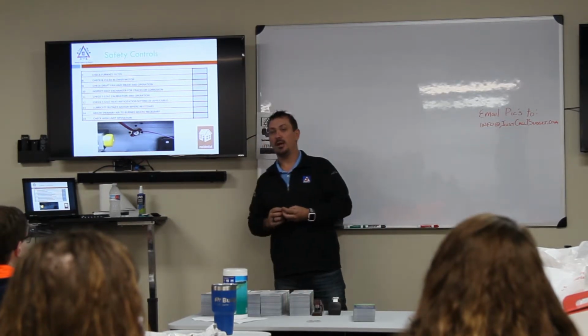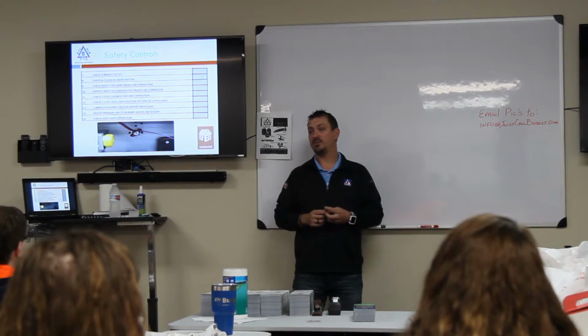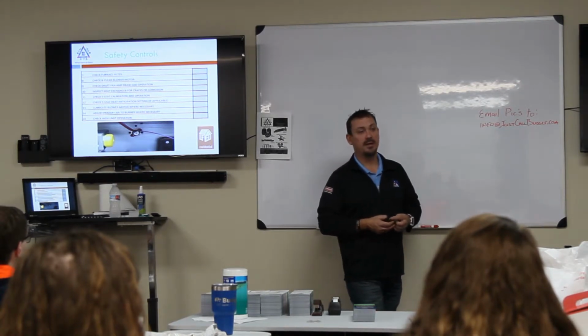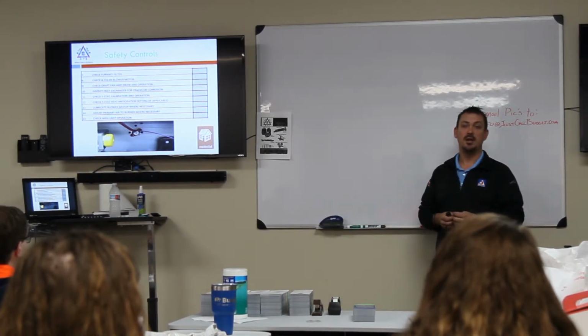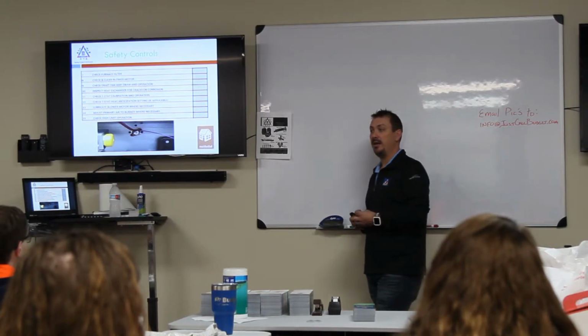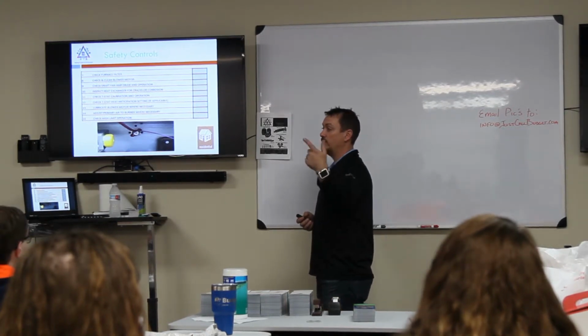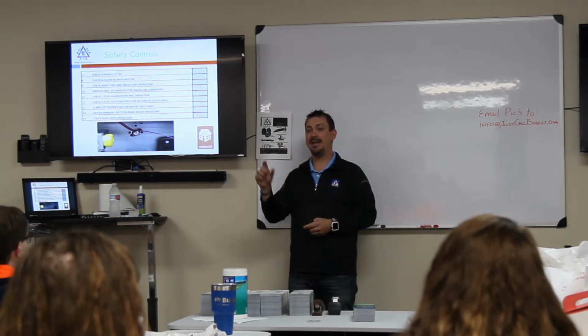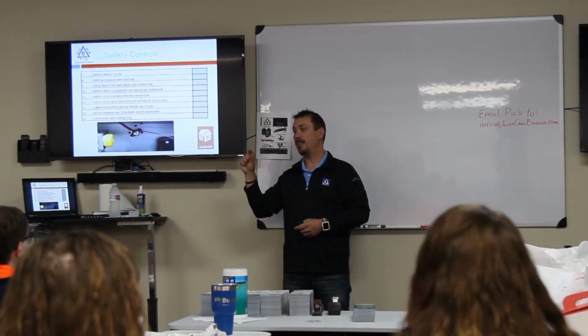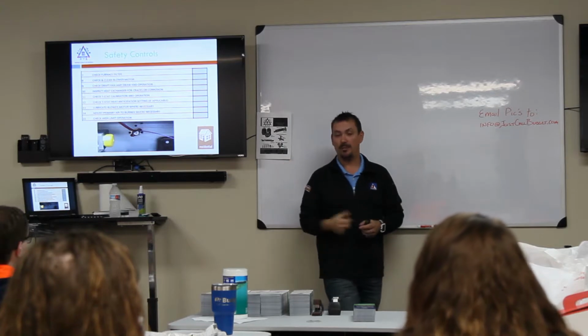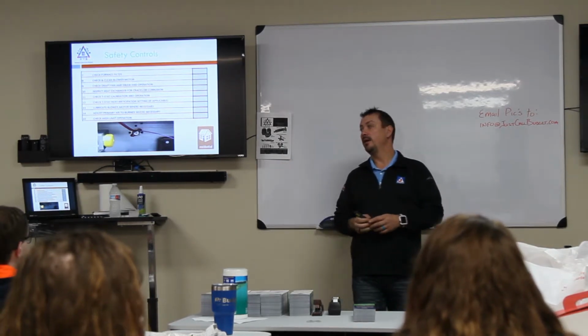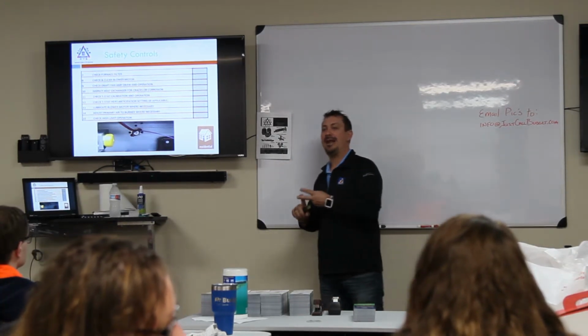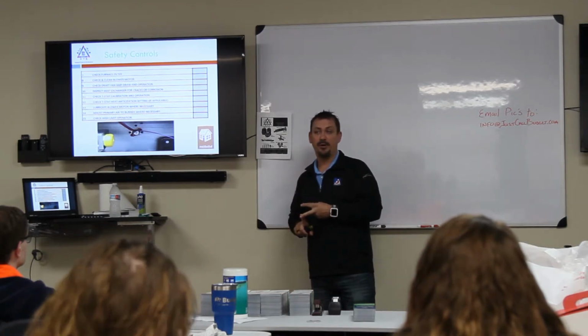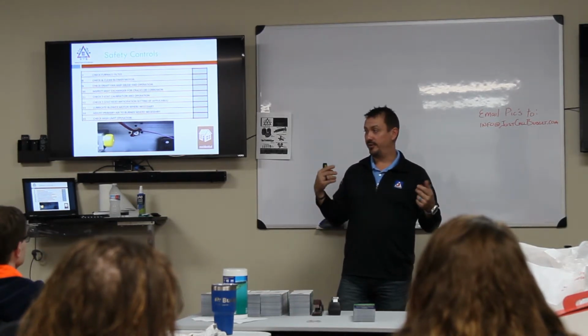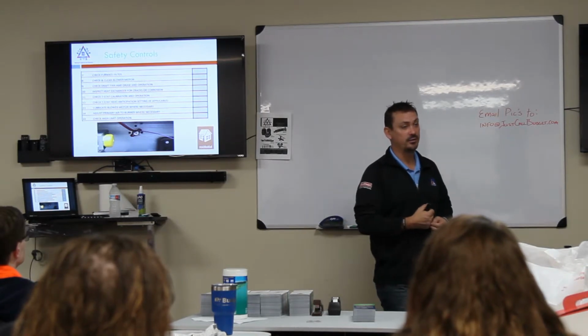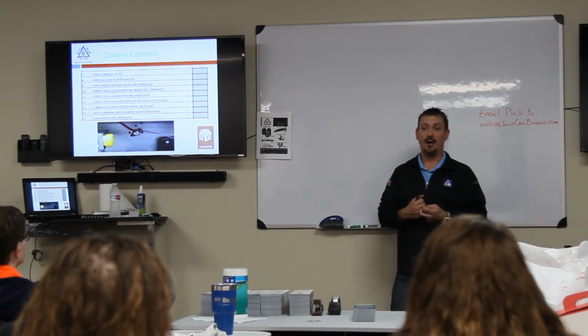Check the pressure switch. That's where that dual port digital manometer will come into play again, where you can check to see what the actual draft of that equipment is at, what the inducer motor is pulling. And what you'll do is you'll take a barbed T and 2 hoses, and your manometer is what will be needed. Now the UEI dual port digital manometer and the Fieldpiece manometer both come with the T's and the extra hoses that you'll need to do this check and this test with.